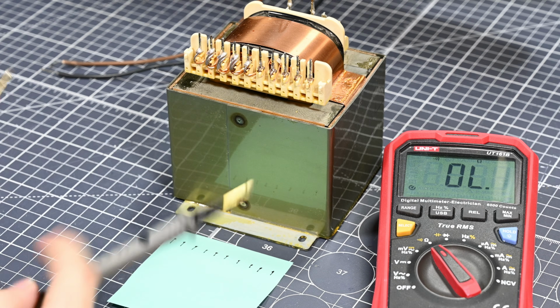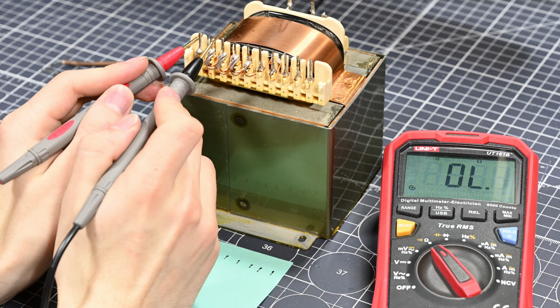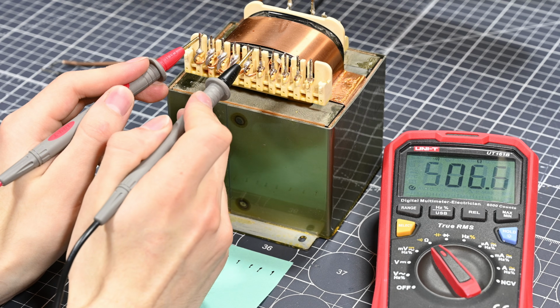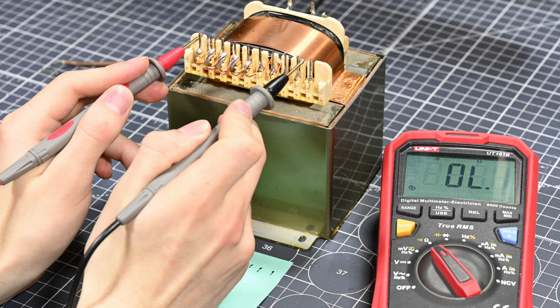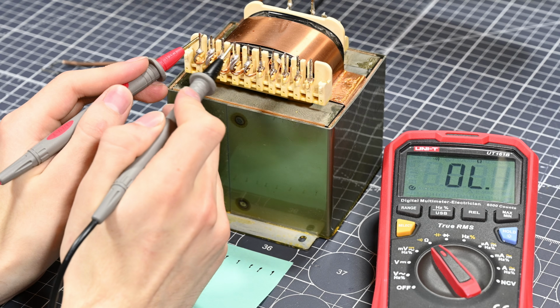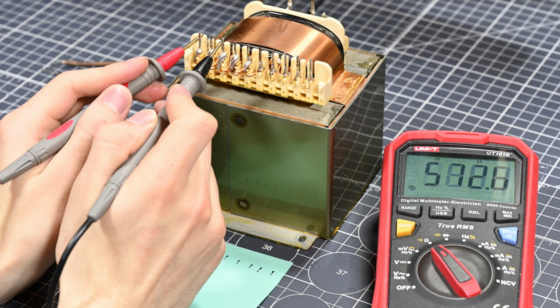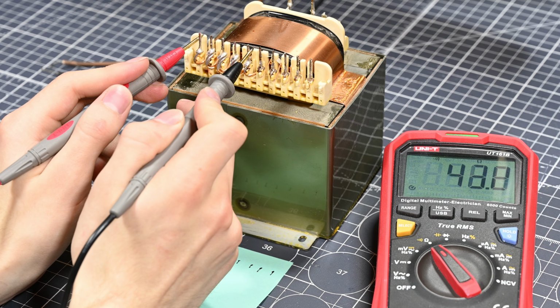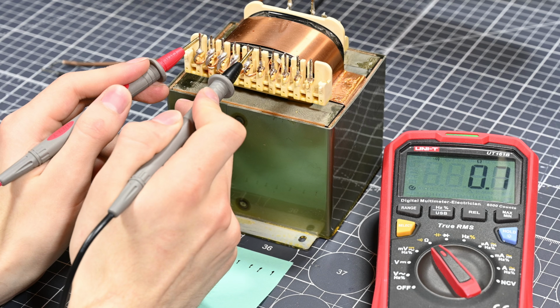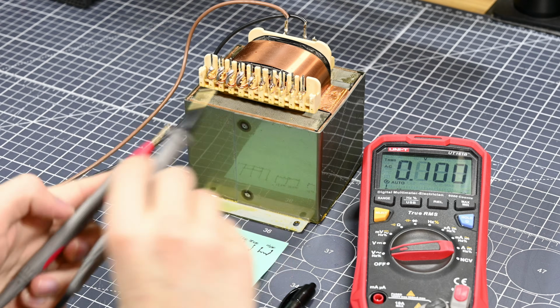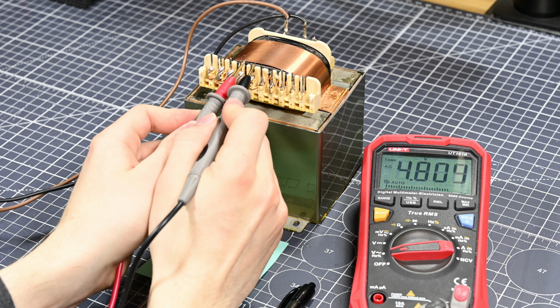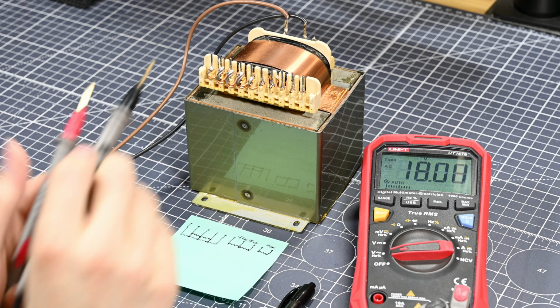Since these transformers usually have many secondary windings for different currents and voltages, the first step is to measure the continuity between the different secondary terminals with the transformer unpowered. This gives us a basic diagram of how the transformer is wired, and later we can do voltage checks.